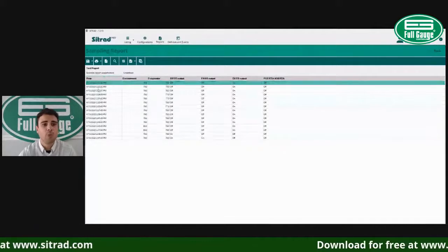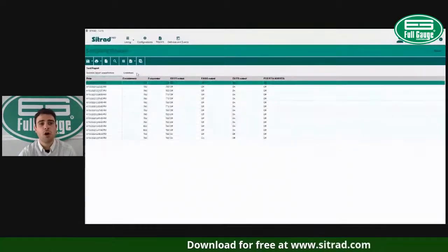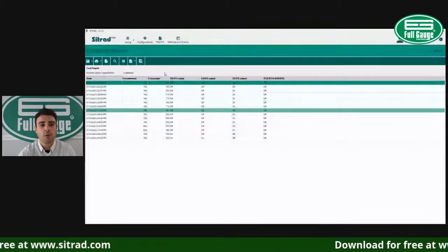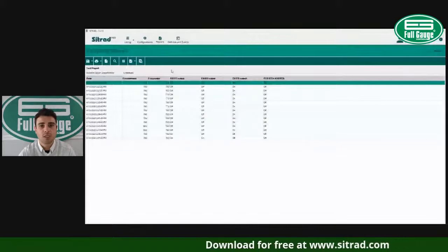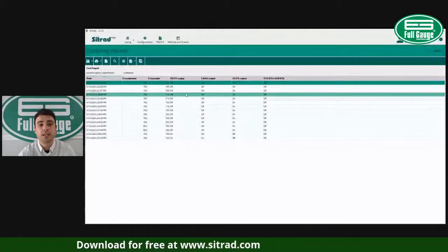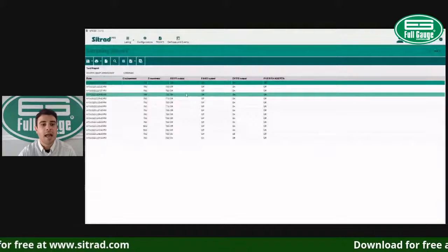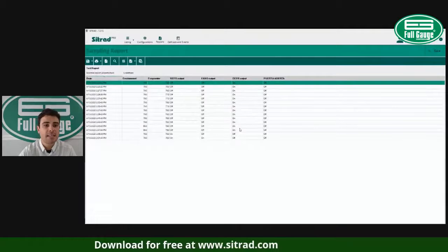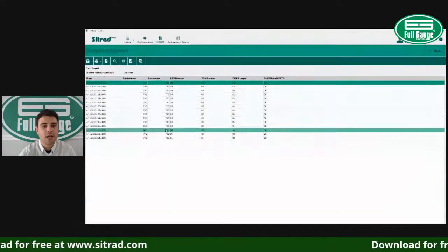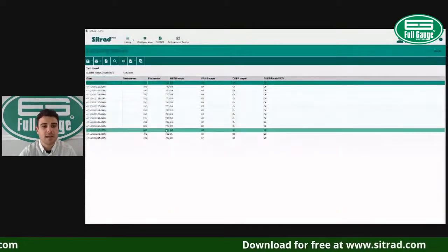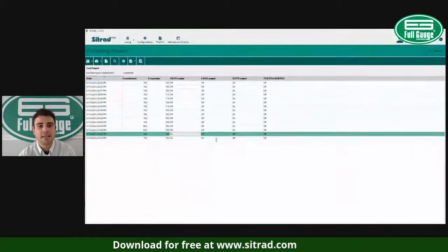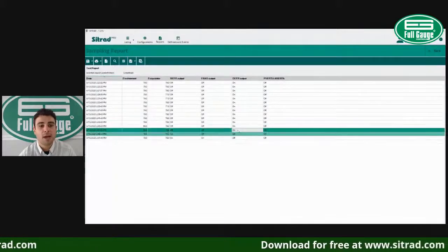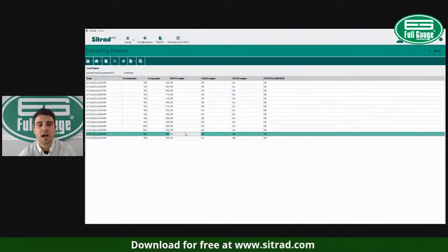And now we can see what was the room temp, the box temperature, and the coil temperature during that report period. And also whenever my compressor was on. Here we can see that the compressor was off, because there was a defrost cycle on. And during the last 10 minutes, our defrost cycle went off and the compressor went on. And here's one interesting thing. Here you can see when the defrost went off, switched from on to off, and now my compressor is on and the fans are off.